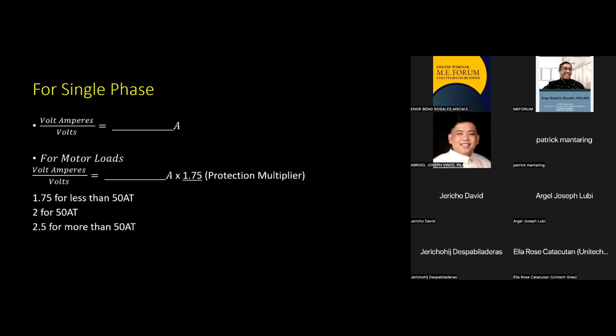Why? Kasi itong 1.75 na ito, kasama na yung mga different factors, yung derating factor, yung continuous load factor, yung overload factor, etc. According to the PEC, the Philippine Electrical Code 2017, the 1.75 minimum factor is your pinaka-minimum na multiplier. Hindi ka na pwede bumaba diyan, pero pwede ka tumaas.